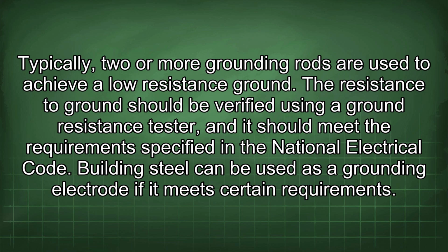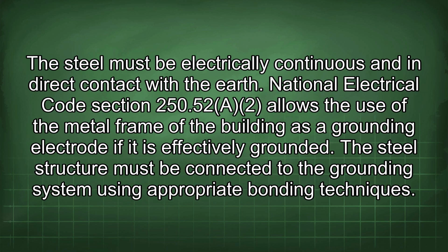the National Electrical Code. Building steel can be used as a grounding electrode if it meets certain requirements. The steel must be electrically continuous and in direct contact with the earth. National Electrical Code Section 250.52(A)(2) allows the use of the metal frame of the building as a grounding electrode if it is effectively grounded.